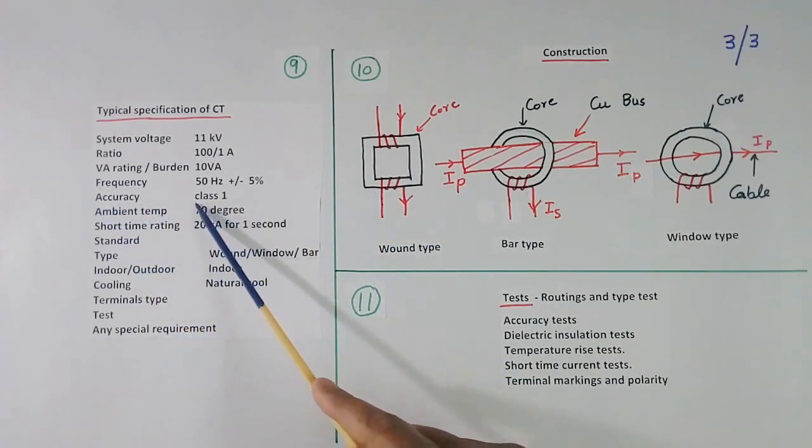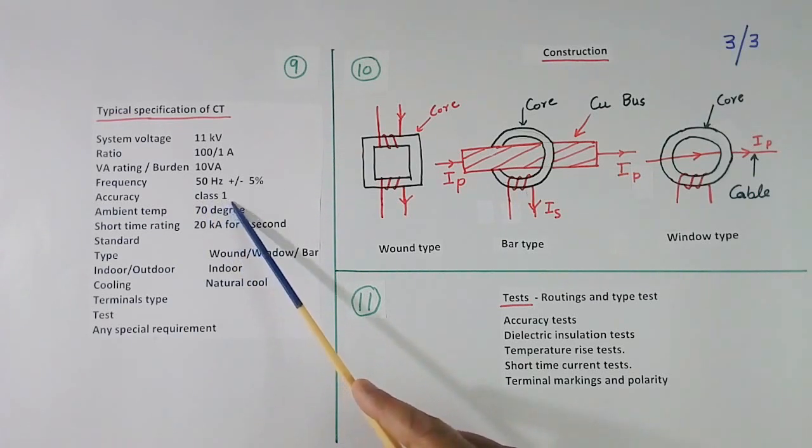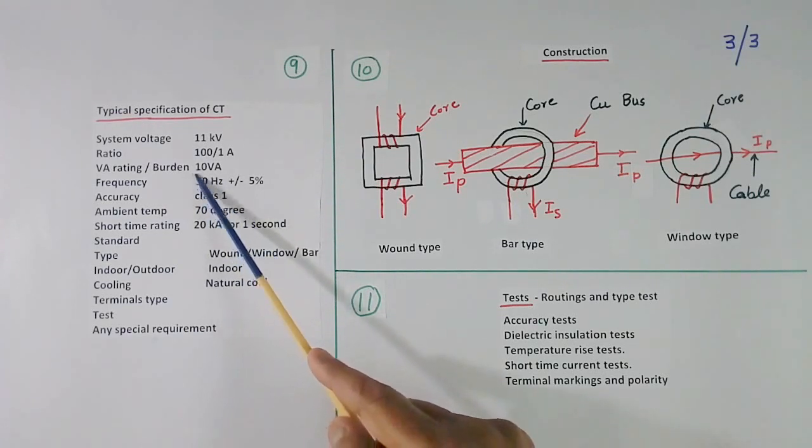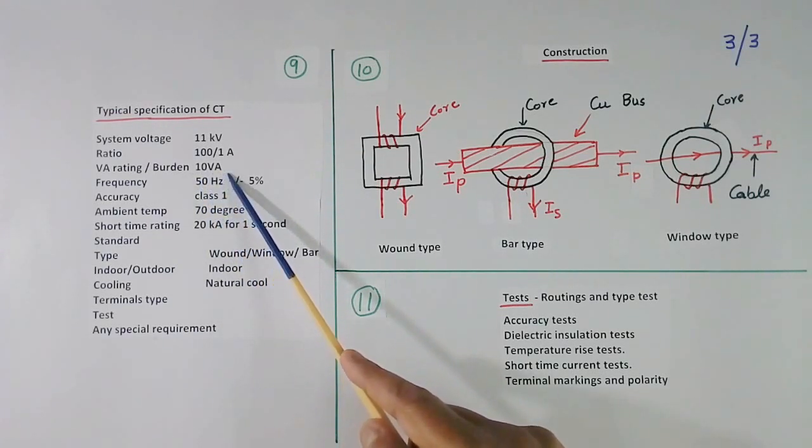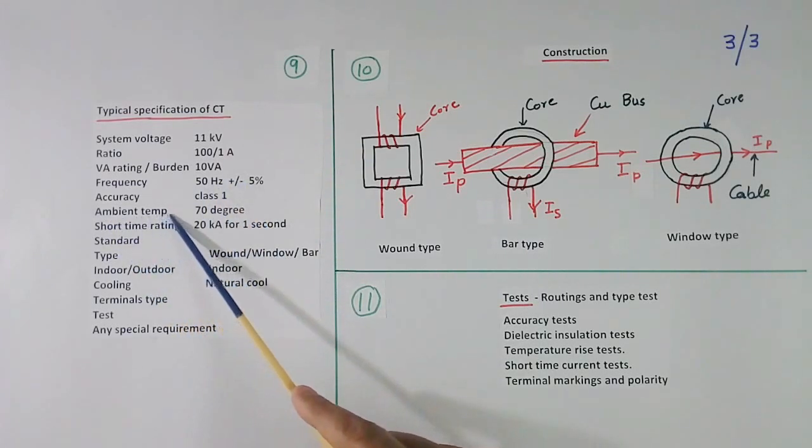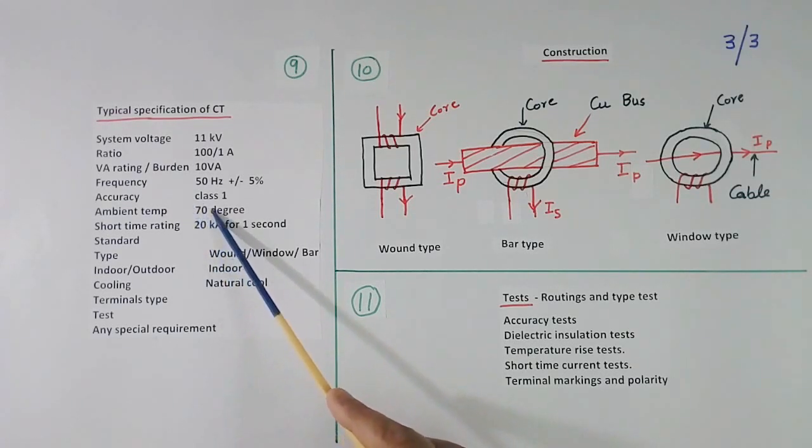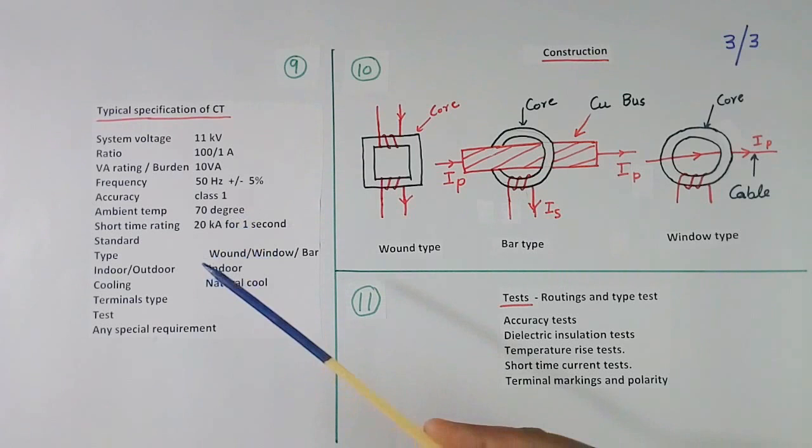Then we will tell accuracy, like class 1. Class 1 means 1% accuracy at rated burden. Then we have to tell ambient temperature, 70 degree or some other. Industrial grade CT will have 70 degree ambient. You can tell 50 or 45 if you want to use for commercial application.